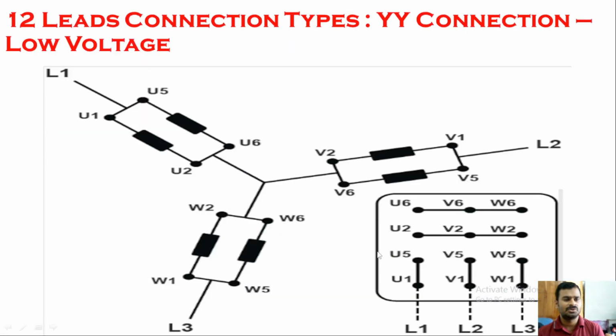And here the next one is 12 lead connection type, star connection or low voltage configuration. Here, what is the difference between the previous one, the 9 lead terminal, and the 12 lead connection? So here none of them are connected by the manufacturer. All the wires are kept outside, and you are going to connect it the way you need. Either you want it in a star connection or in a delta connection.